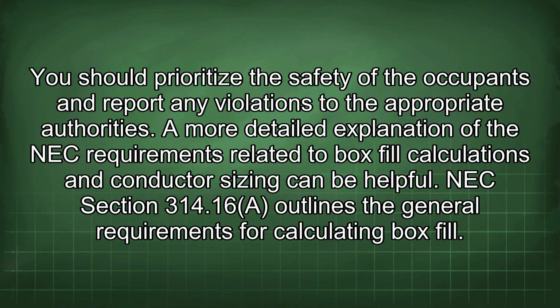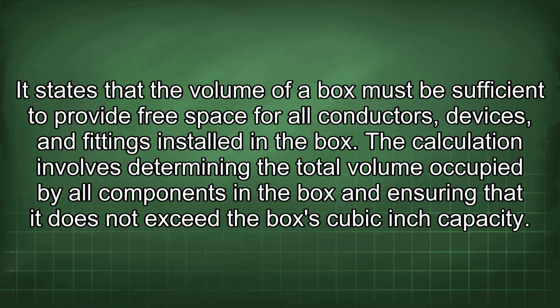You should prioritize the safety of the occupants and report any violations to the appropriate authorities. A more detailed explanation of the NEC requirements related to box fill calculations and conductor sizing can be helpful. NEC Section 314.16 outlines the general requirements for calculating box fill. It states that the volume of a box must be sufficient to provide free space for all conductors, devices, and fittings installed in the box.